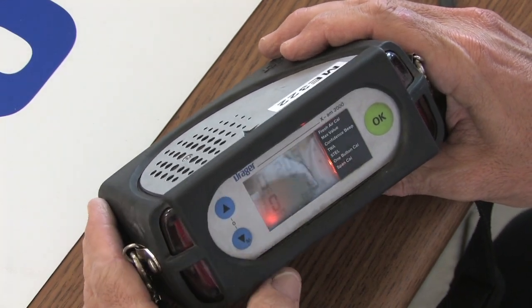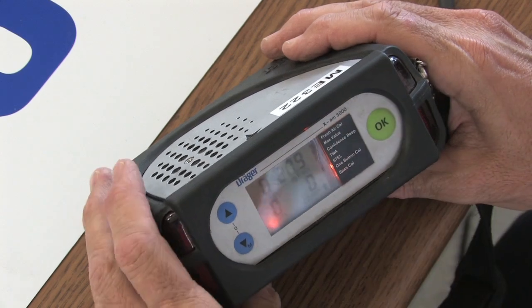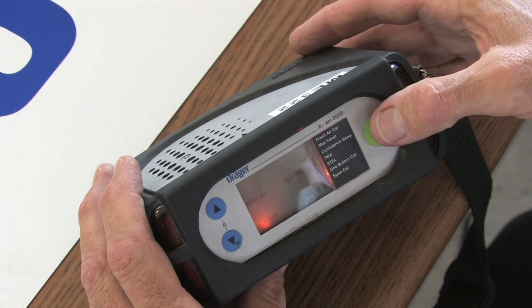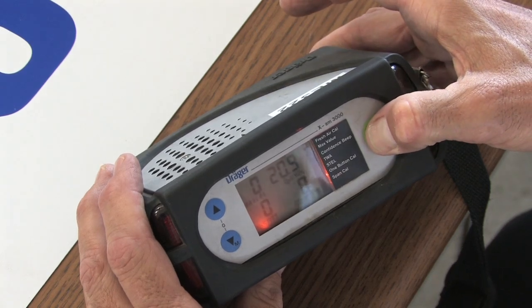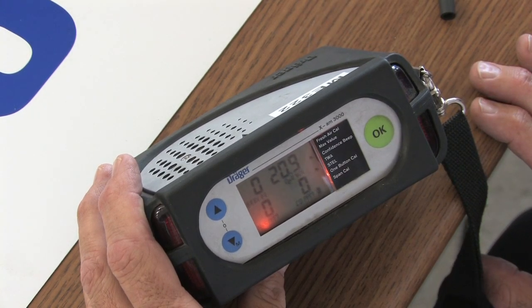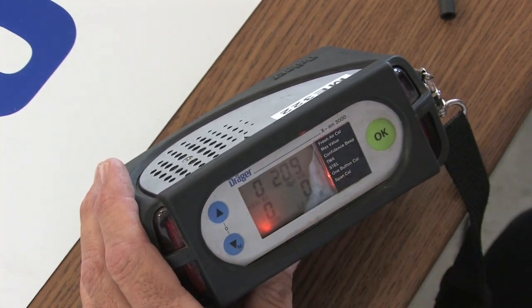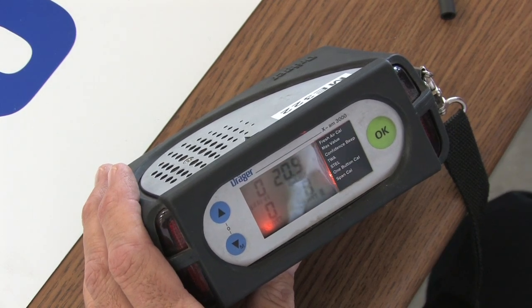I hit this button once. Fresh Air Cal is now blinking. I'm going to hit the OK button, and then all the sensors blink. I hit the OK button again. They continue to blink, but I see the word OK, which is telling me I'm going to have a successful Fresh Air Cal. I hit it a third time and wait for it to time out. I hit it a fourth time and now it times out. Sometimes on the X-am 3000s, these touch pads, you have to hit them twice to get them to proceed — they're a little touch sensitive.